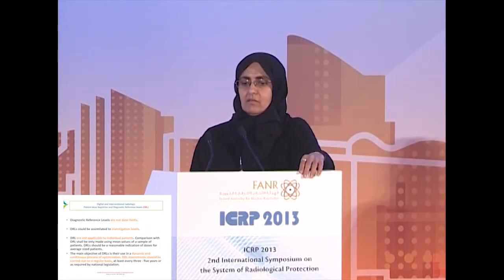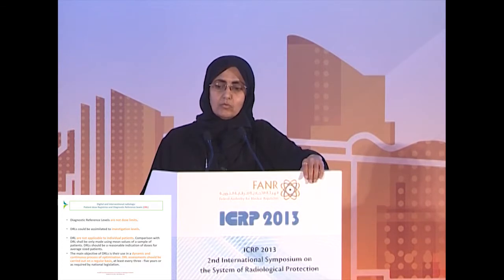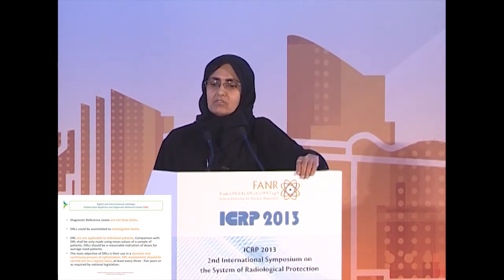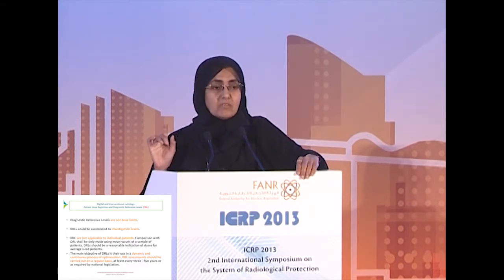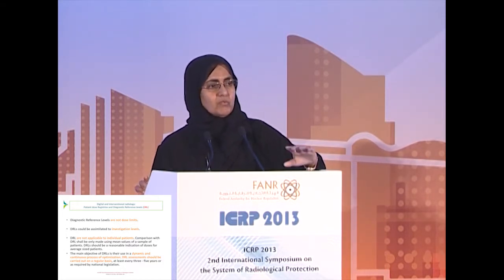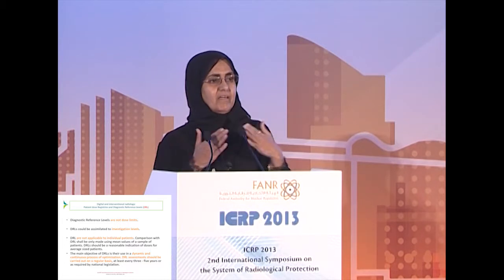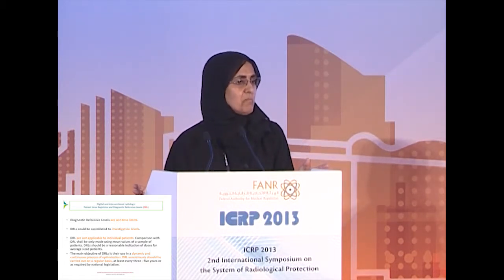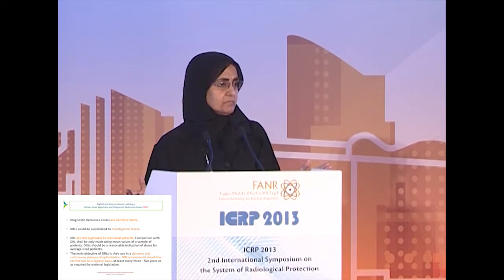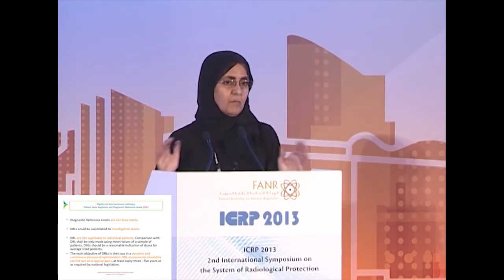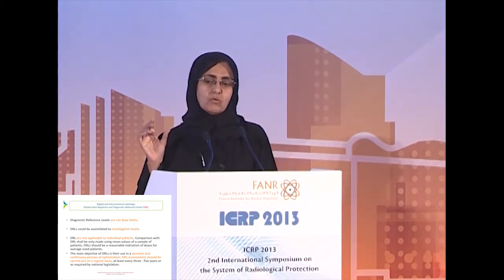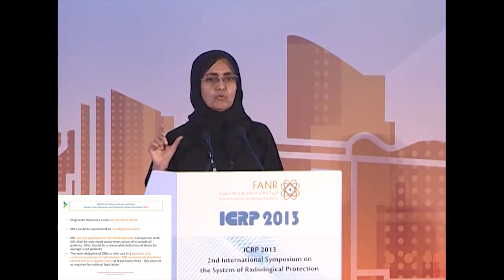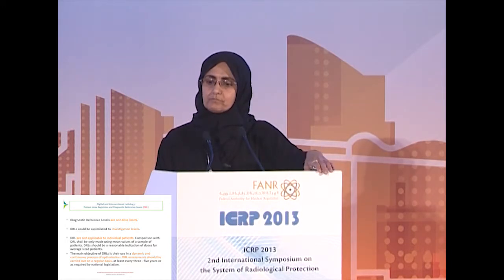As I said, diagnostic reference levels are not dose limits. They are like investigation levels. They are not applicable to individual patients. So what we have to do is carry out a survey on a minimum of 20 common examinations, and we also have to consider the size of the patient, because this affects the value of the dose.